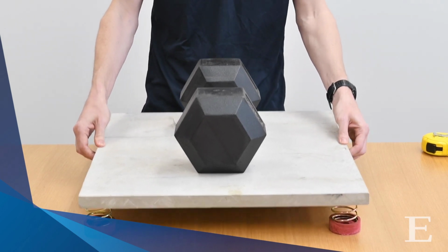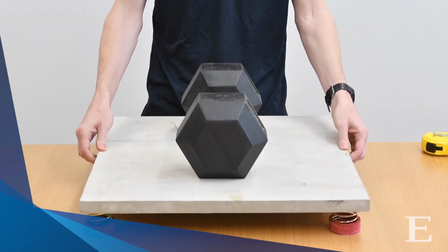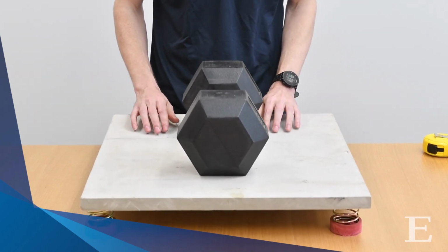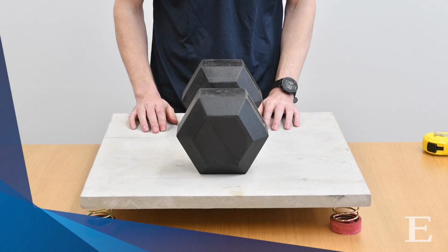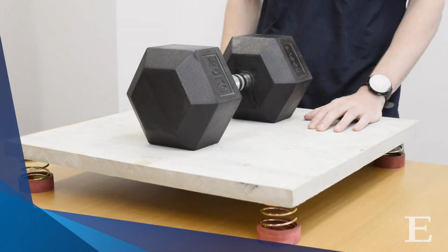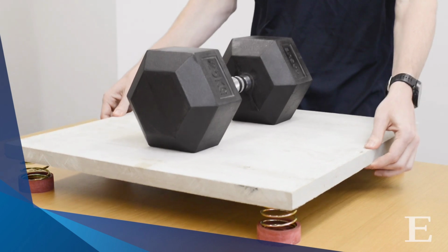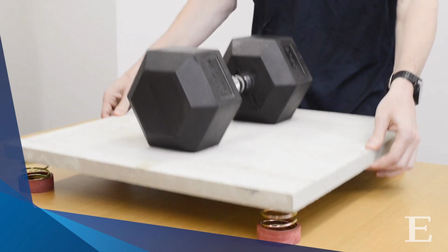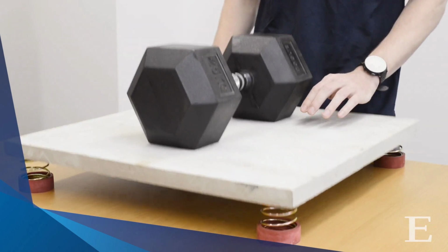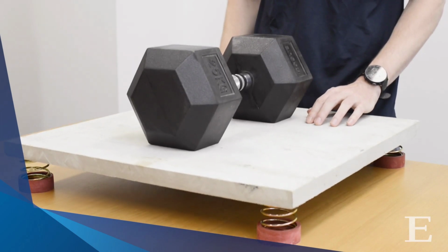If the speed of our rotating machinery on top of the platform matches the natural frequency, then that's what a resonance occurrence is. And we only start isolating when the speed is significantly higher than this. In fact, the higher the speed of your rotating machinery relative to your isolator frequency, the better your theoretical isolation performance. So the operating speed of the plant will be one of the major factors in how much static deflection is deemed acceptable.